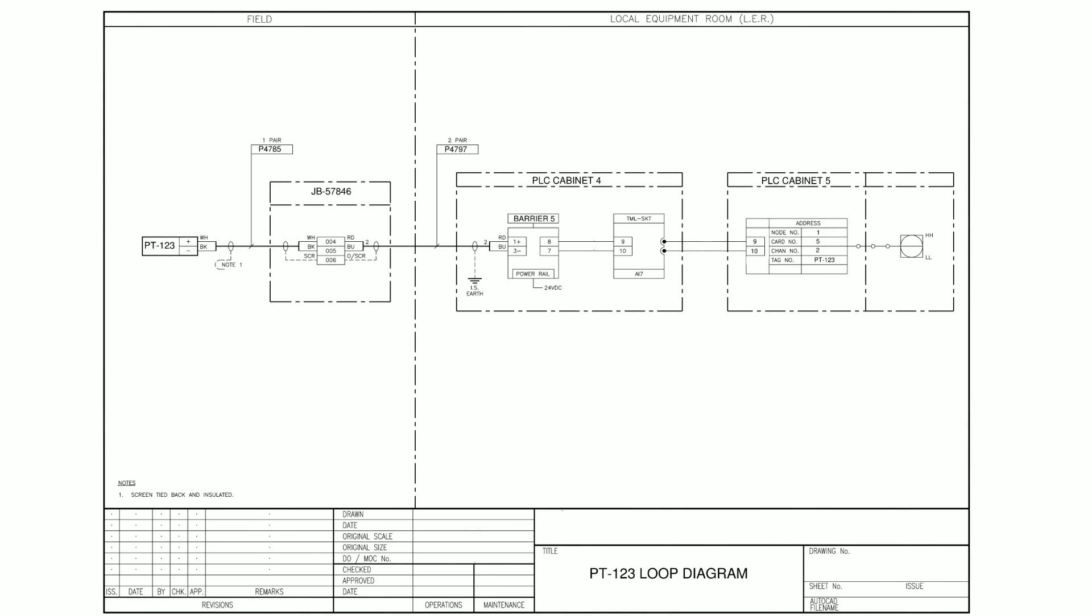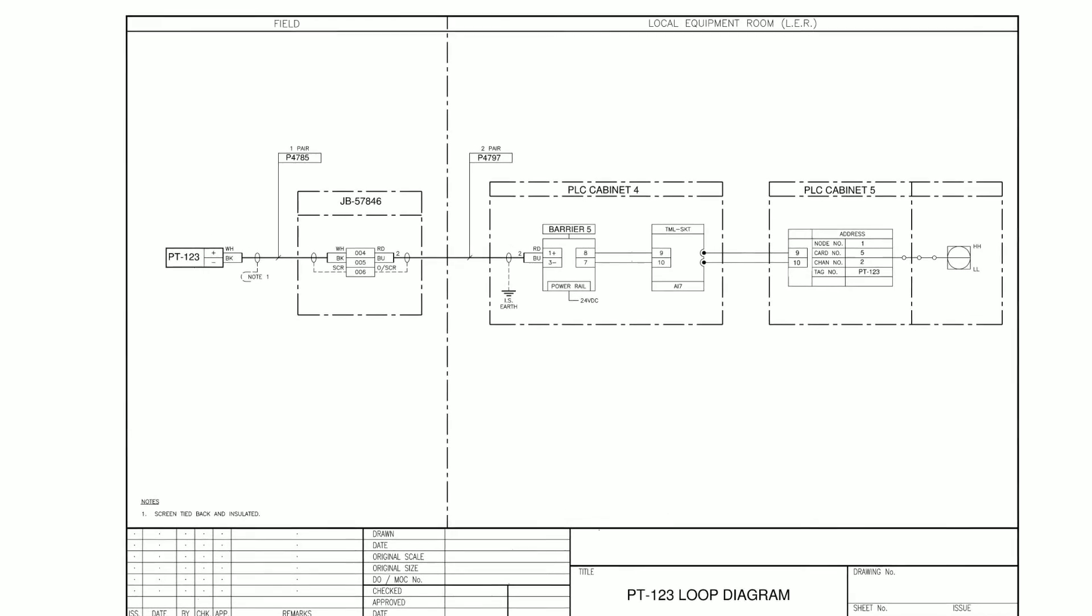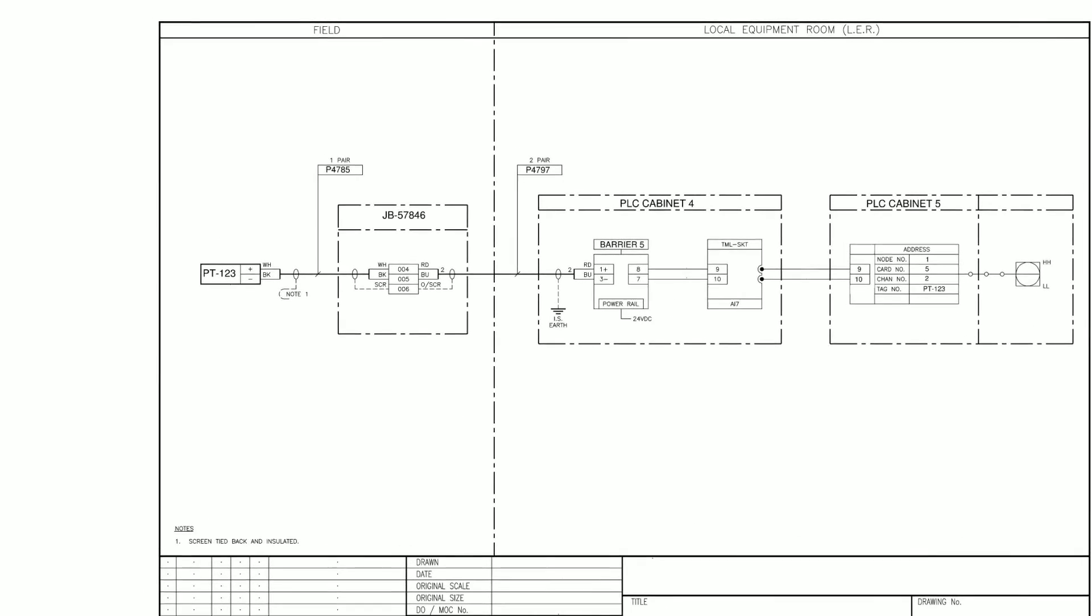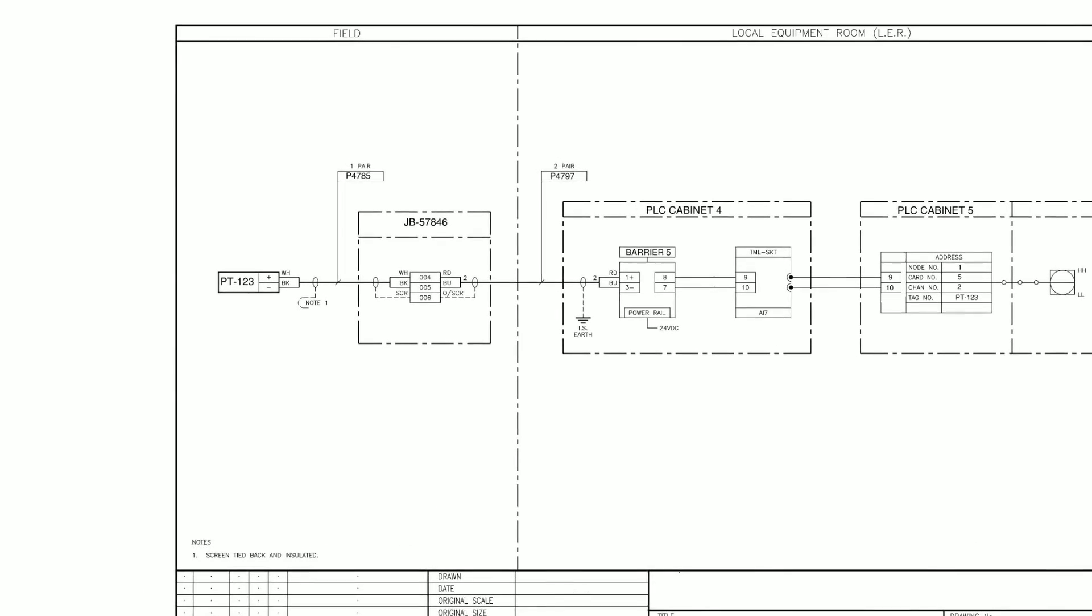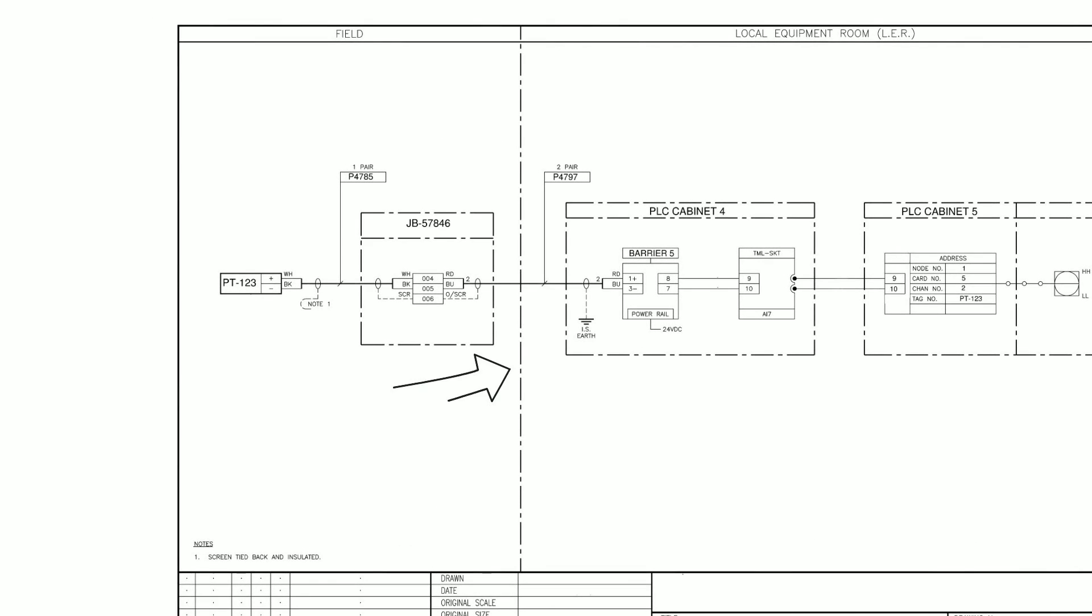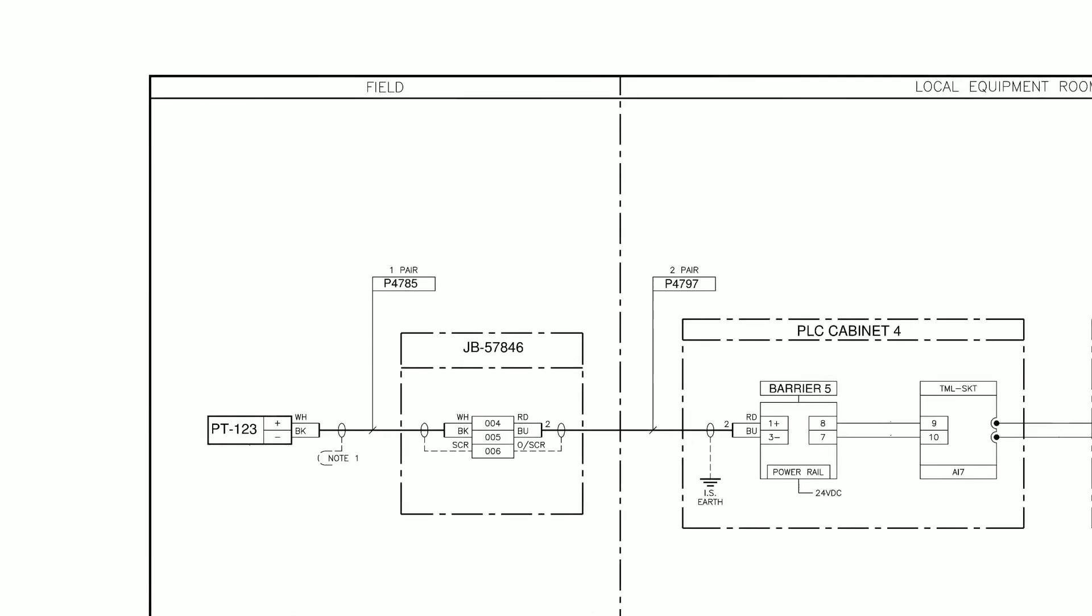Okay, onto the actual loop diagram itself. Let's point out all the information we can see on our drawing. Firstly, if we look down the center of the loop diagram, you can see a vertical broken line. This is used to separate the different physical areas the equipment goes through on your site.